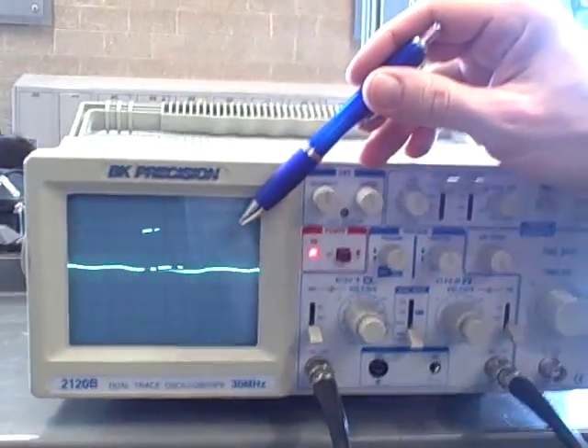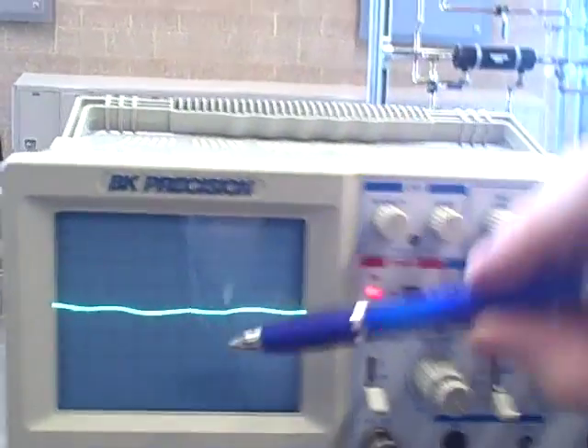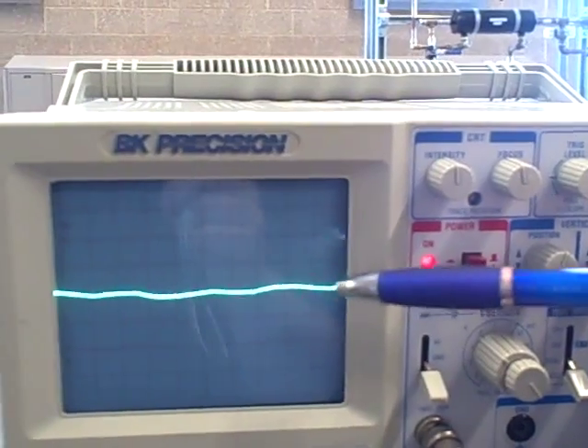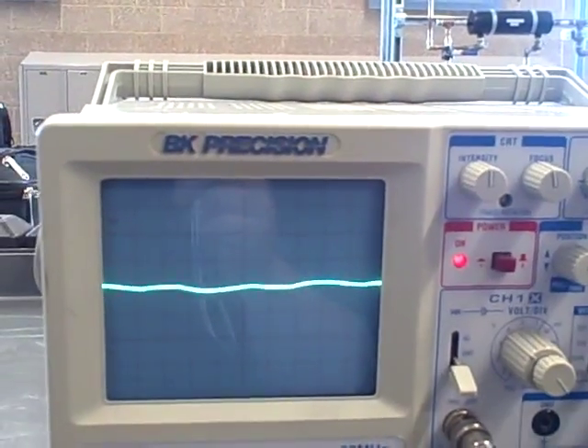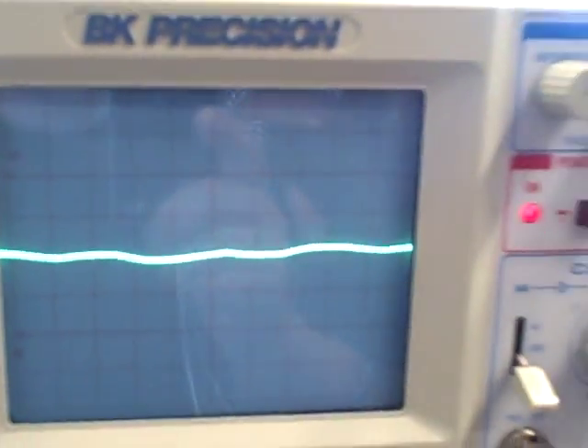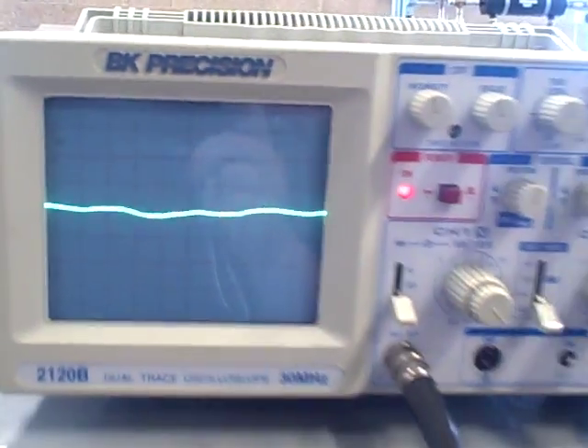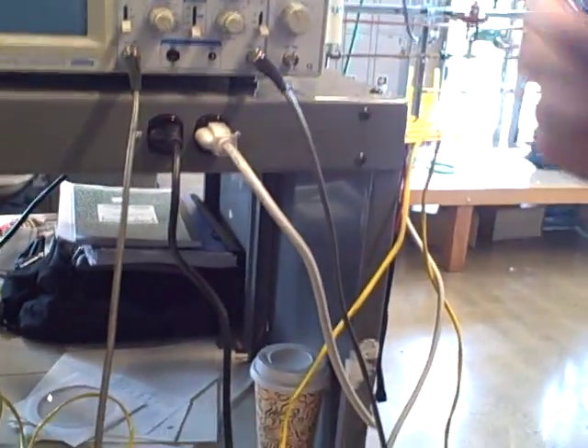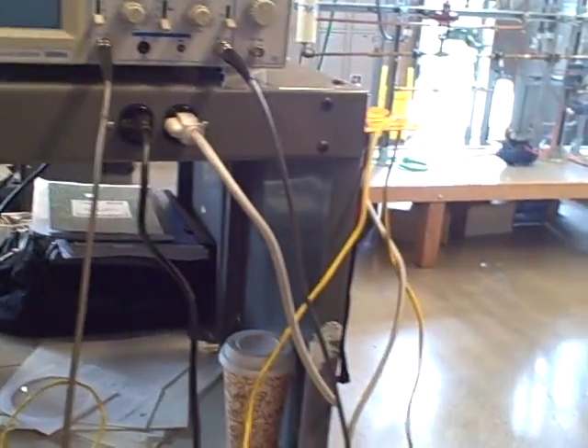If we look at the scope, we can see the pattern of data right here. You see a little bit of quiescent noise, a little bit of AC noise right there, and then you see the bursts of data going up and down. That's the RS-485 signals using Modbus to format the bits representing characters sent to and from the controllers.